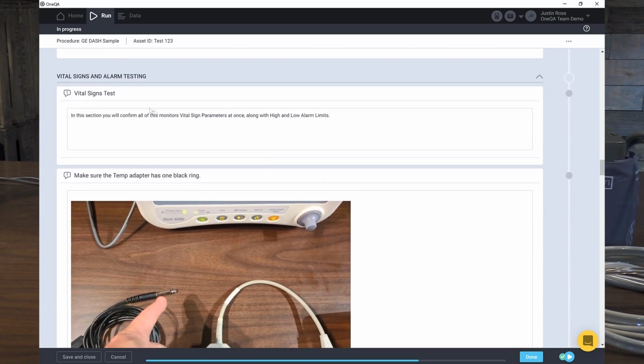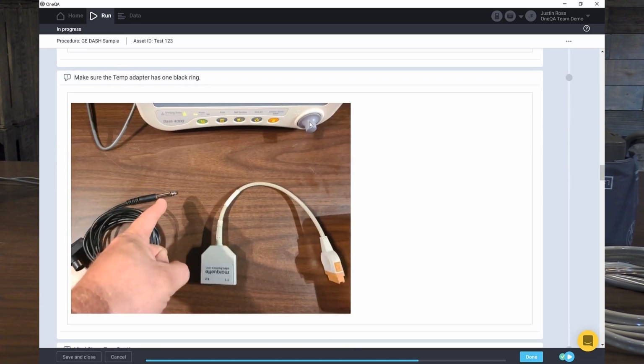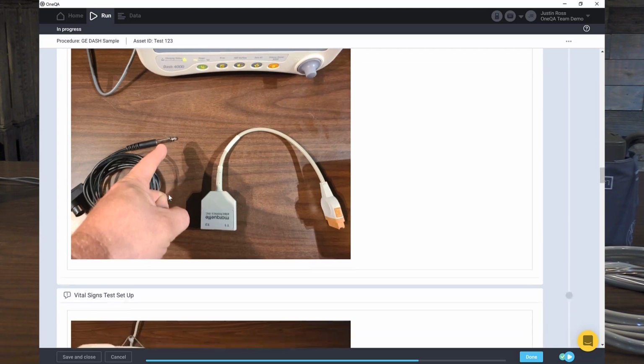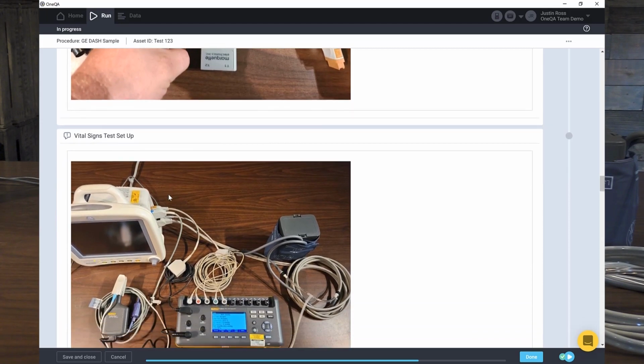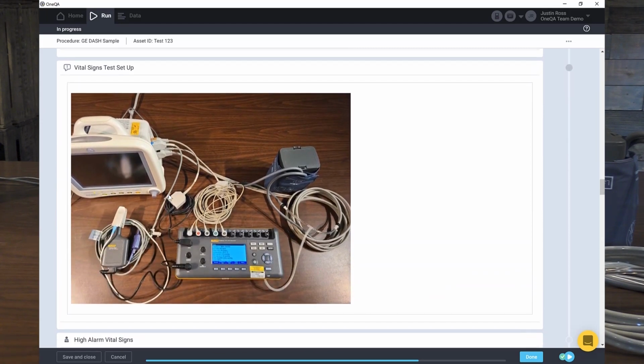The next step is we're going to do the vital signs and alarm testing. Here's our instructions. We're going to test the high and low limit alarms. And I put a special instruction in here because yesterday when I was setting up, I grabbed the wrong temperature cable and it had the 2 black rings. I need the one with 1 black ring. So I have the verbiage and a picture right here showing me to use this temperature probe adapter. And then I scroll down and here's exactly how I need to set this up.